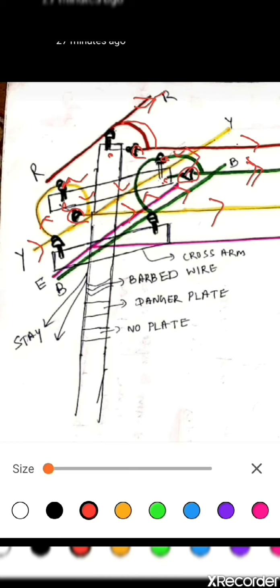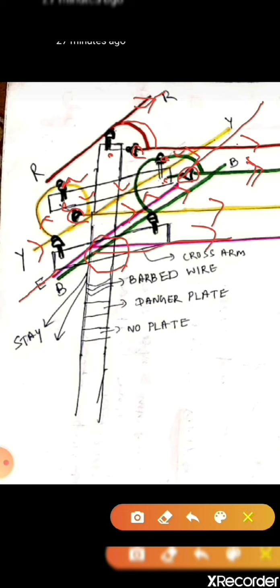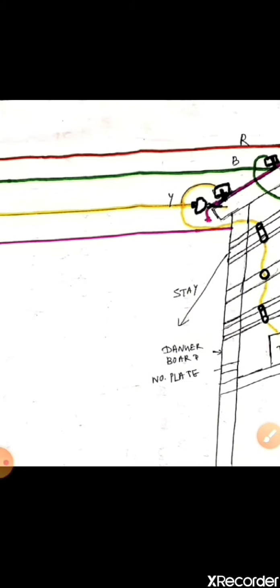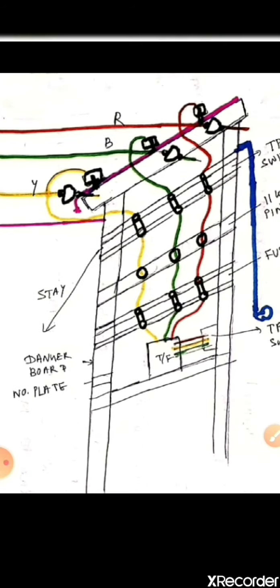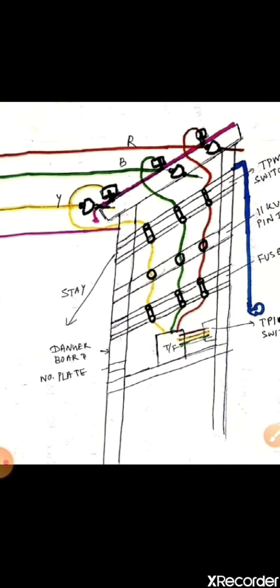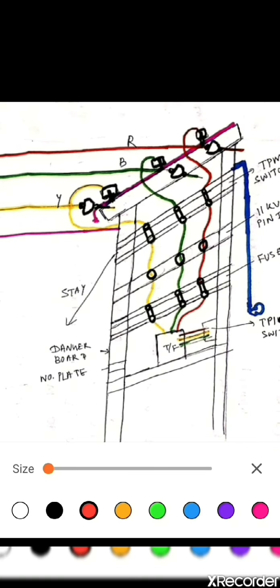And this is your earth line, going along this direction, and we have to take the connection of the earth line along this direction. So you need to connect one earth wire clamp. Again, here the connections are going along this direction, and the three phase lines and the earth wire are connected on this pole mounted substation.